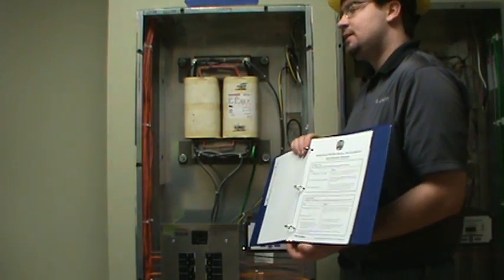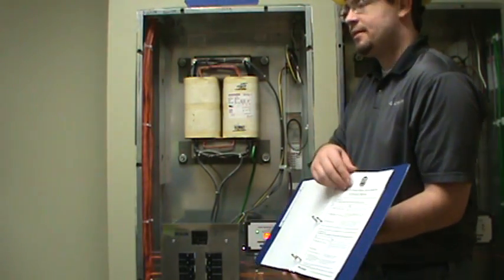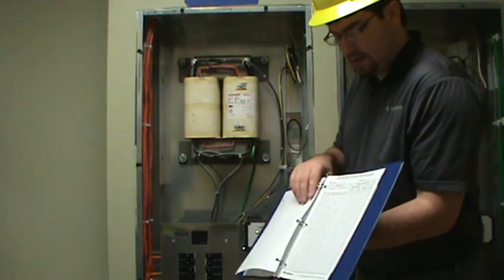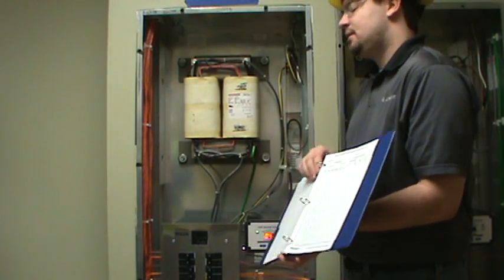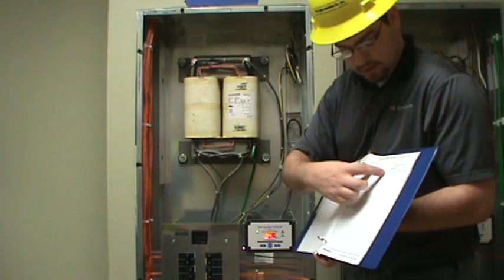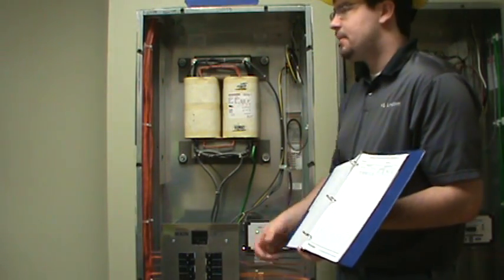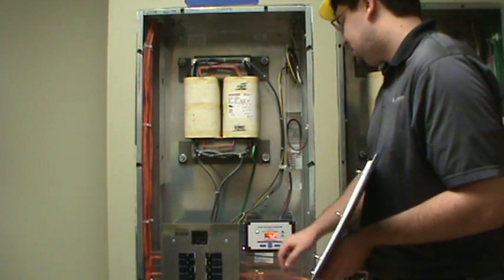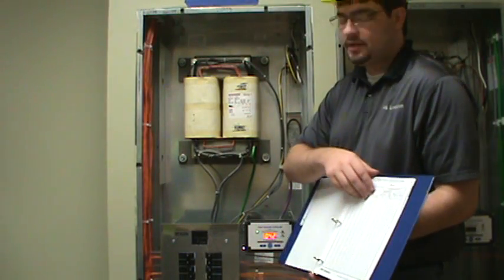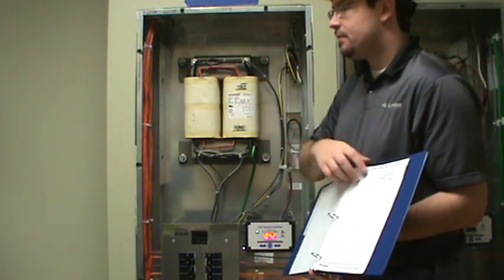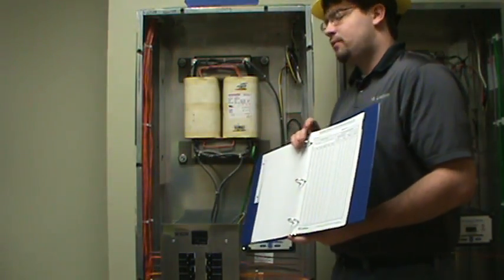Here is that annual test. Pretty simple. Written it down in case you guys need it. And here's where you can record your test. This portion here would be the part that's required by code. Just holding that test button, watching the lights move the way they should. And this part is what we recommend as a manufacturer. Sort of what I'm doing today.